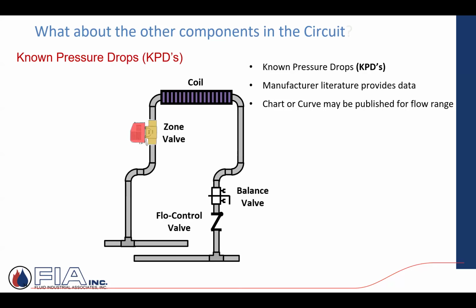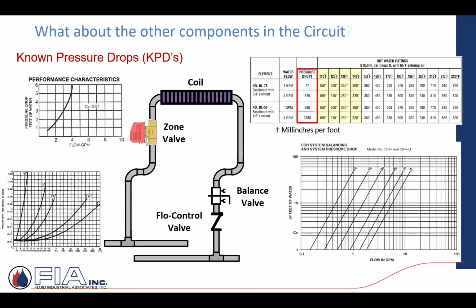And then, once you get past that, what else is in that system? Is there a boiler? Is there a fan coil? Is there a control valve? Is there a balance valve? So they have what they call these KPDs. It's just known pressure drops. So a lot of manufacturers will have literature that helps us. It's all online nowadays. But it will say, hey, I got this zone valve, just for argument's sake, a control valve, a zone valve. I have a performance chart that says, hey, depending upon the flow rate, I know what the pressure drop's going to be.